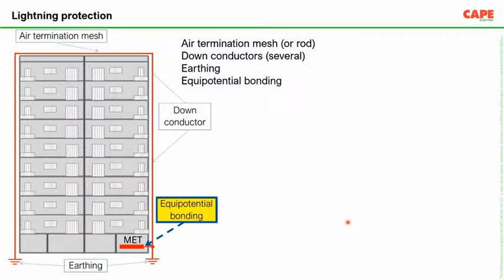It is very much necessary that the down conductor and the MET are equipotentially bonded. There shall be a direct connection, or there can be a connection through a spark gap. This connection is mandatory, whereas in most of the places I am seeing this connection is absolutely missing.